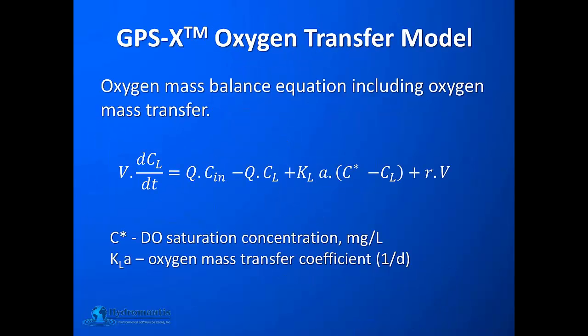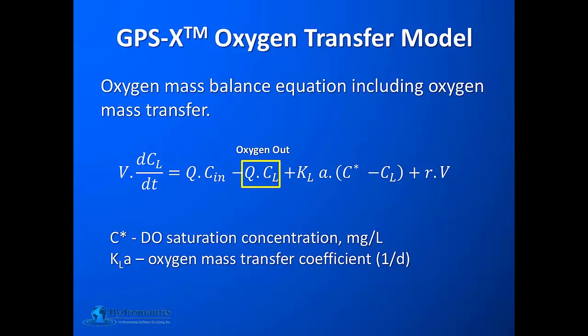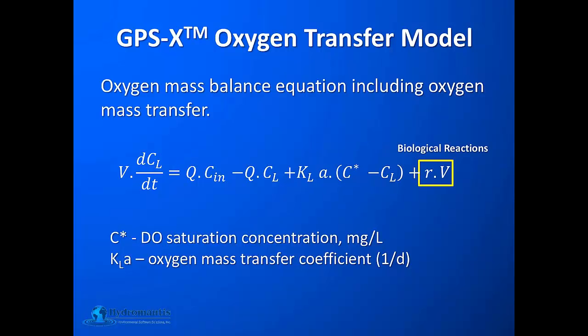Today I'll be talking about both models: the oxygen transfer model, which we've discussed previously, but I'll give a brief background on how the equations are set up in GPS-X; and then the air delivery model, which is a new implementation in GPS-X 6.5. To model oxygen transfer, we start with a mass balance equation for dissolved oxygen concentration. The rate of change of oxygen is given by oxygen coming in, oxygen going out, oxygen added through gas-liquid transfer, and the biological reactions consuming oxygen.